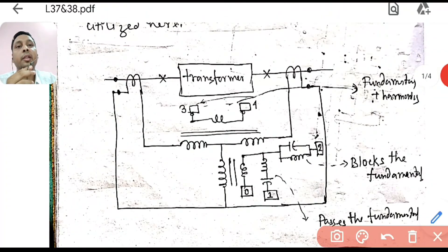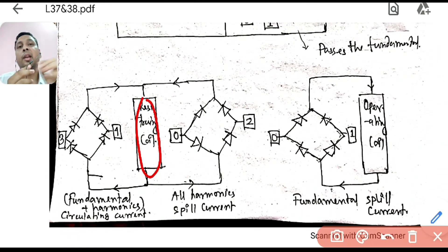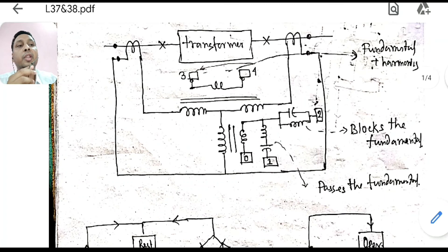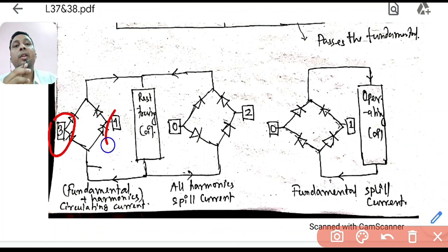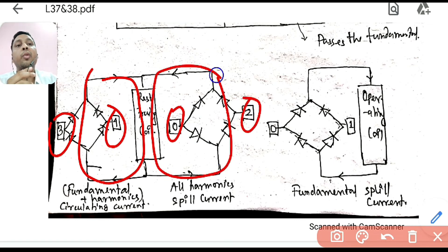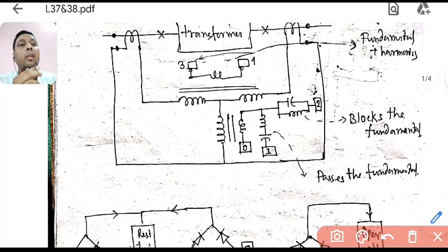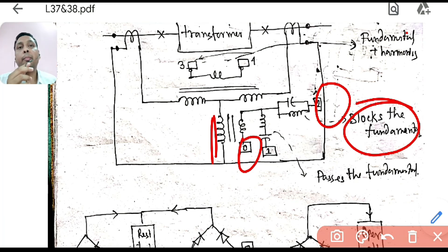Now for the relay connection: the restraining coil in the relay is fed from terminals 3 and 4, which carry the normal restraining current — the same as in normal percentage bias protection, so there is no change there. Additionally, terminals 0 and 2 are also fed into the restraining coil. Terminals 0 and 2 measure the harmonic component of the spill current. In case of a fault, this harmonic value will be negligible, but during inrush it will be very high, providing extra restraining current.